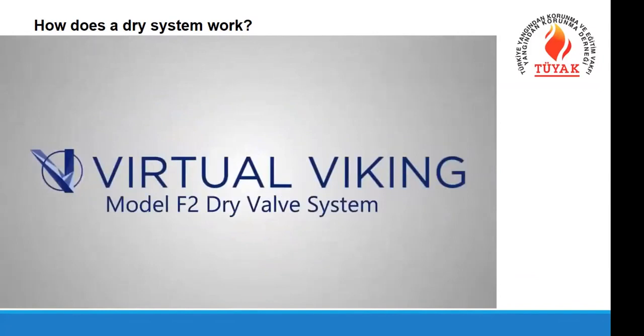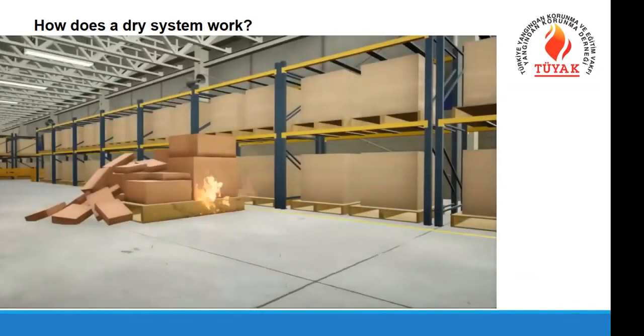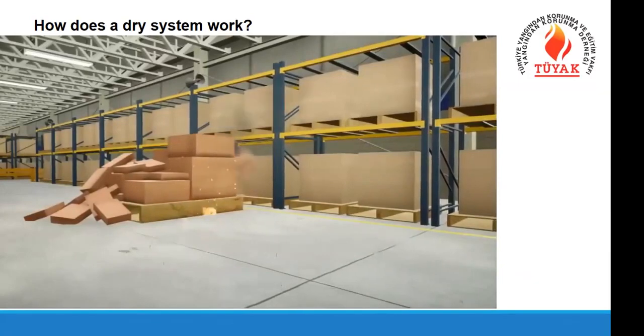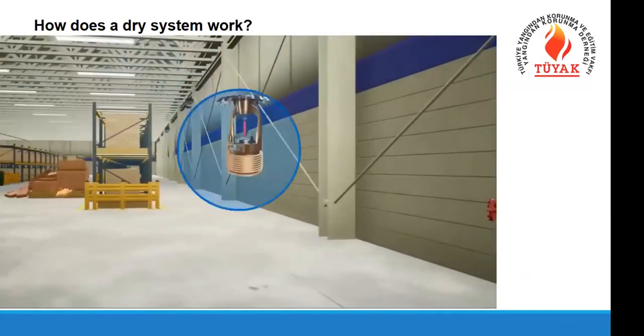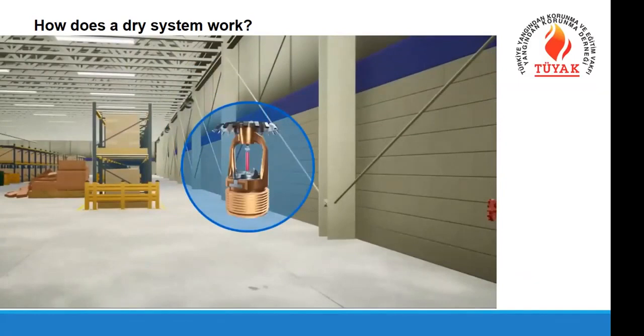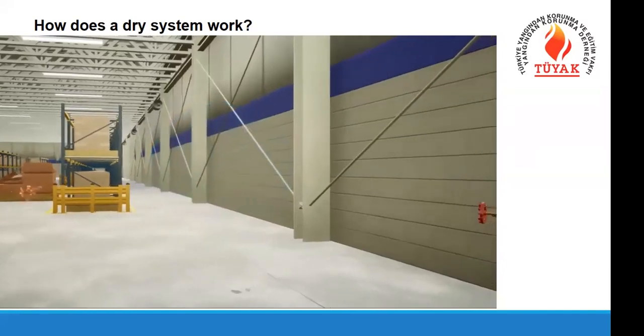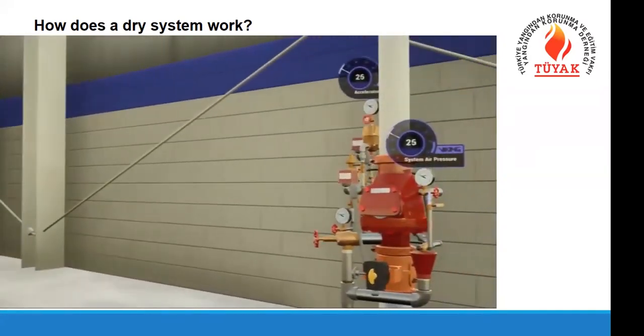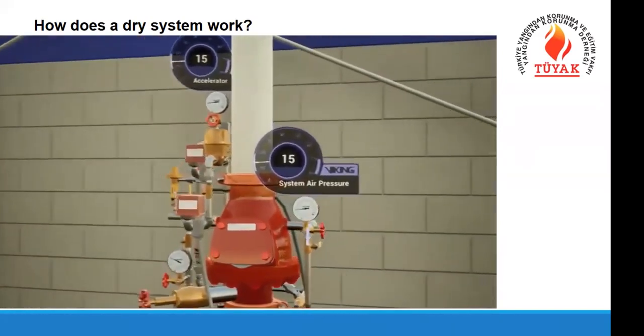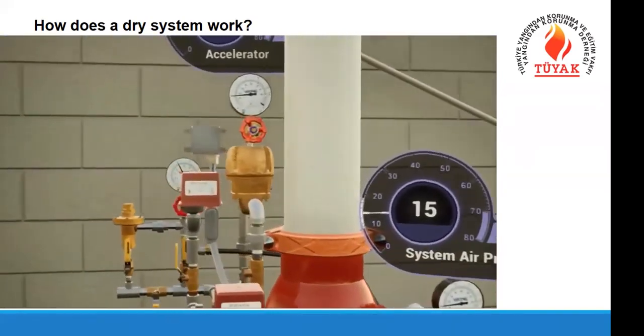These systems are especially used in unheated areas subject to freezing. A fire has started in the building. As the fire grows and the heat reaches the sprinkler's rated temperature, the temperature-sensitive device in the automatic sprinkler operates. The temperature-sensitive device could be a fragile ball or a fusible link. Once it operates, either the pipe cap or the seal will be displaced by air pressure. Air escapes through the activated sprinklers, causing the air pressure within the outlet chamber of the valve, the trim, and the pipes to drop.